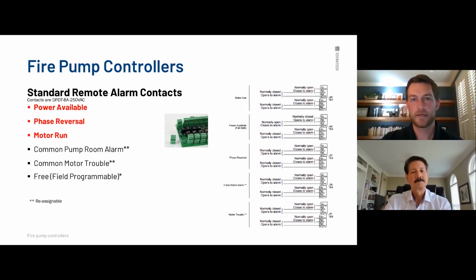Then we have the standard remote alarm contacts. There are three that are required, the ones that you see in red there: power available, phase reversal, and motor run. Those are the three that are required. We also give three additional contacts that can be programmed in the field. It says it's set for a common pump room alarm, which covers a group of alarms, common motor trouble, which covers a group of alarms, and then we have one that doesn't have anything set already.